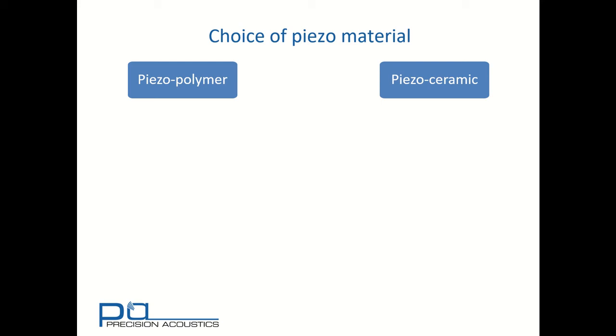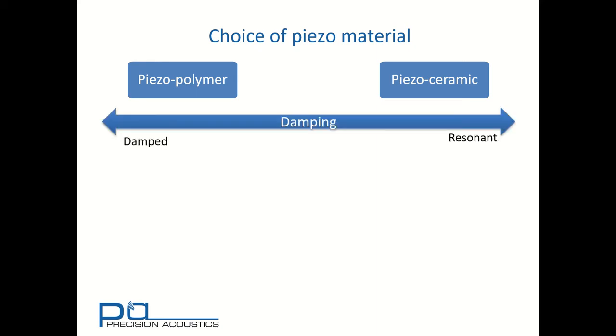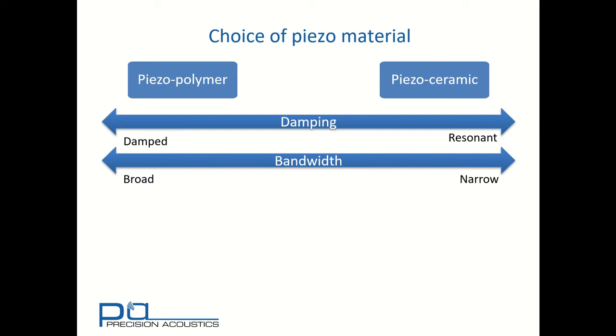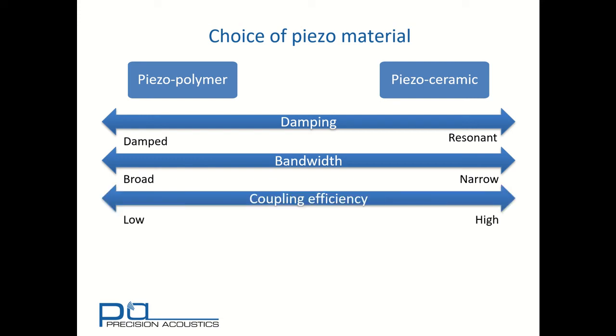It's also useful to see how the choice of piezo material fits within this. We've already mentioned piezopolymers and piezoceramics, but let's look at some of the other aspects. Clearly, we've mentioned that piezopolymers are highly damped and piezoceramics can be highly resonant. We've also seen that the bandwidth is narrowband for a resonant device and much broader band for a damped device. And because we've lost energy into heating, the coupling efficiency tends to be much higher for a piezoceramic device and much lower for a piezopolymer. In this context, we're talking about the coupling from electrical energy to mechanical energy.